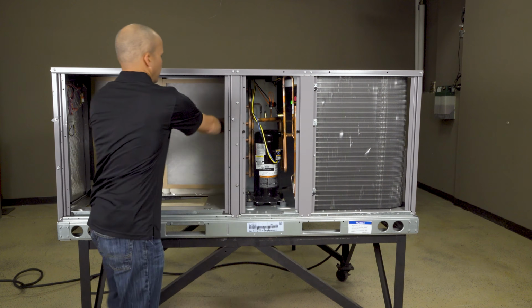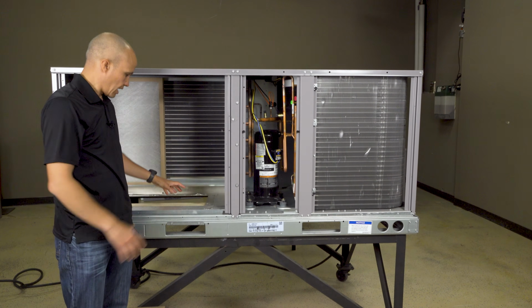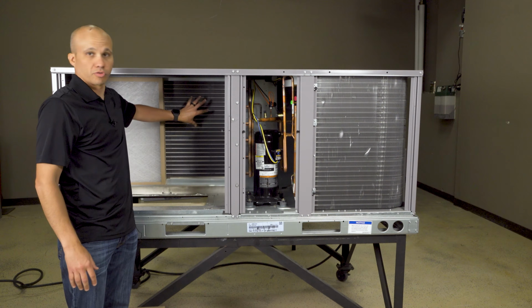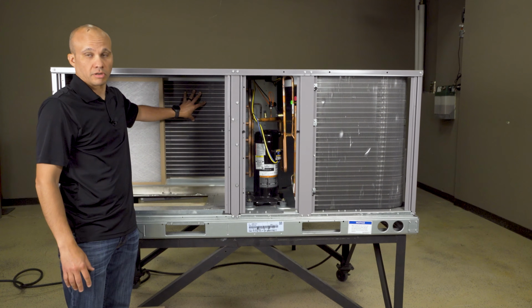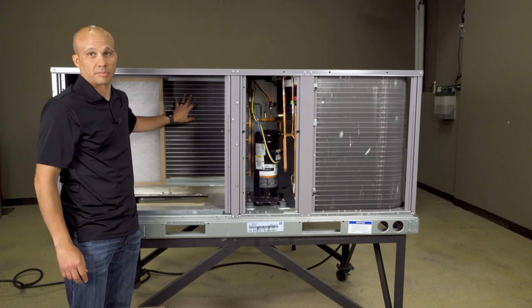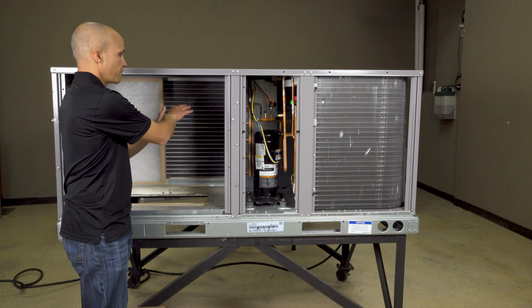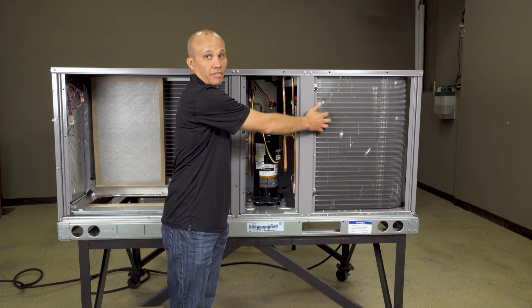All right, so over here, this would be on our roof, obviously. Air would be coming up from the building, going through this evaporator coil, which is going to have cold refrigerant running through it. So it's going to absorb the heat from the air of my building. And there's a fan on the other side that's pulling that air through and sending it back into the building nice and cool. That heat from this coil gets pumped by this compressor over to the other coil.